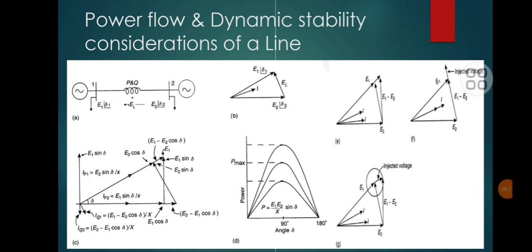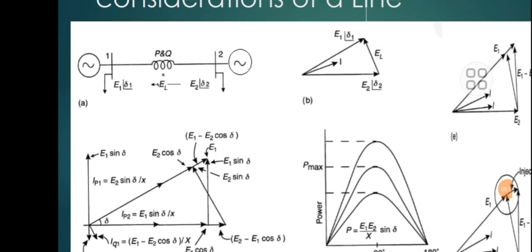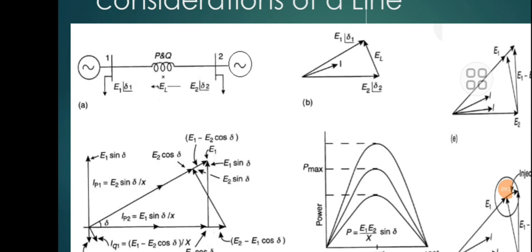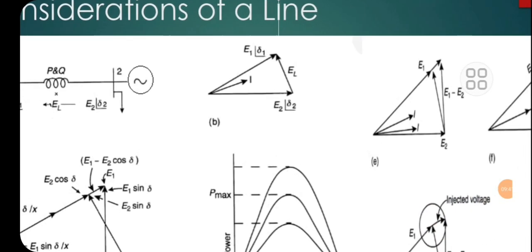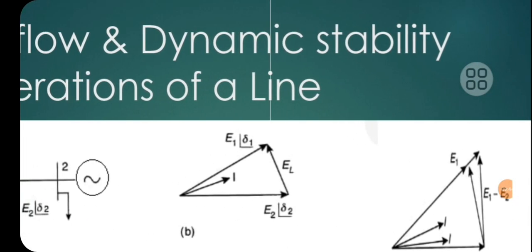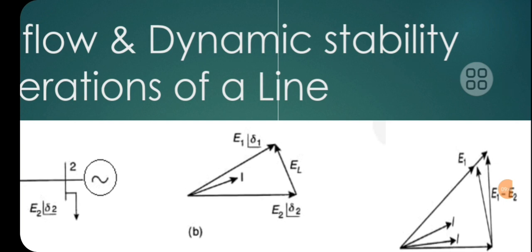This figure shows the power flow and dynamic stability considerations of a line. A simple line is chosen having two buses, and both the buses carry generators as well as load. The bus 1 voltage is E1 at a power angle of delta 1, and bus 2 voltage is E2 at delta 2. So the real and reactive power flows in the transmission line can be calculated easily based upon the basic laws. Figure B shows a phasor diagram relating E1 and E2 voltages. So the difference of these two voltages is the drop in the transmission line, EL, and the current I flowing through the transmission line is a vector perpendicular to EL always.